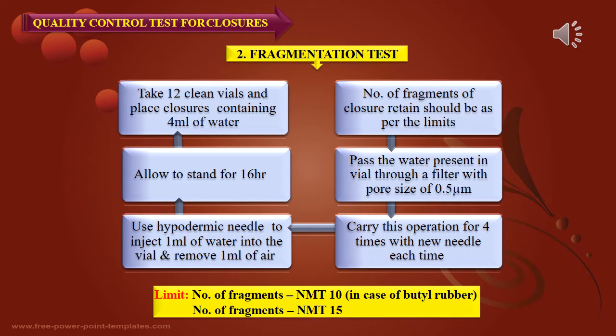For the fragmentation test, take 12 clean vials and place closures containing 4 ml of water, then allow to stand for 16 hours. Use a hypodermic needle to inject 1 ml of water into the vial and remove 1 ml of air; carry this operation 4 times with a new needle each time. Pass the water through a filter with pore size of 0.5 micrometers. Number of fragments retained should not be more than 10 for butyl rubber, and not more than 15 for other rubbers.